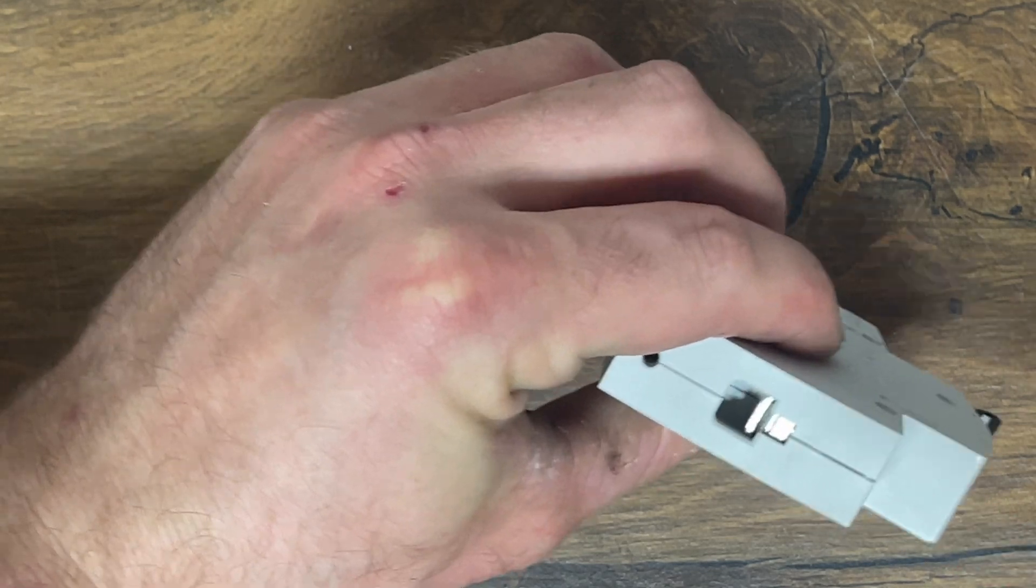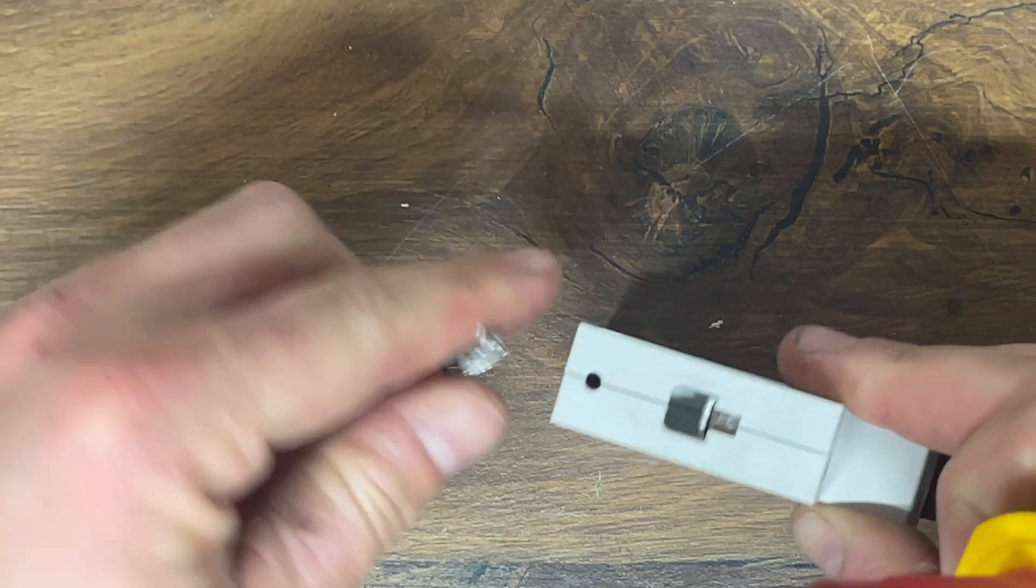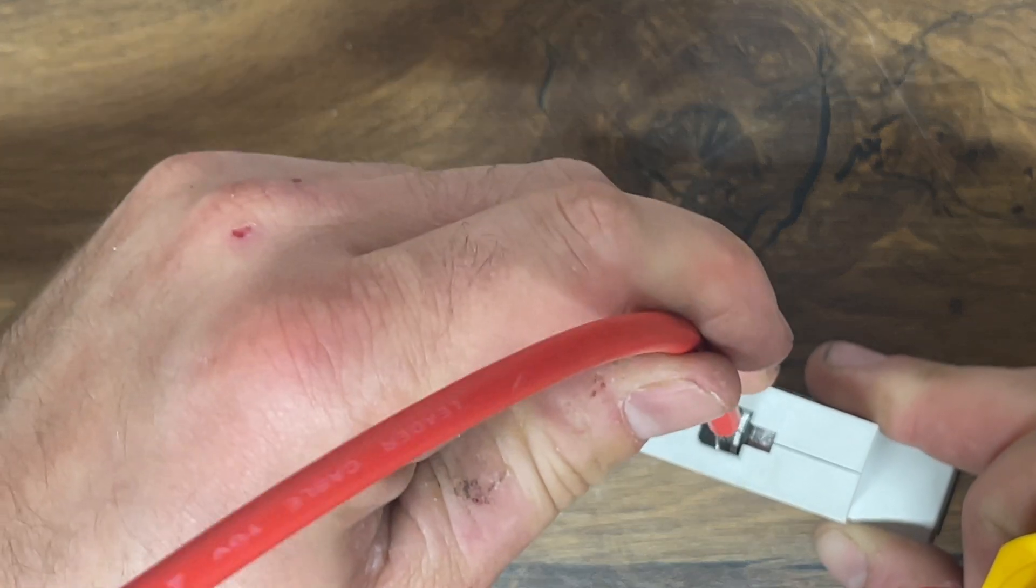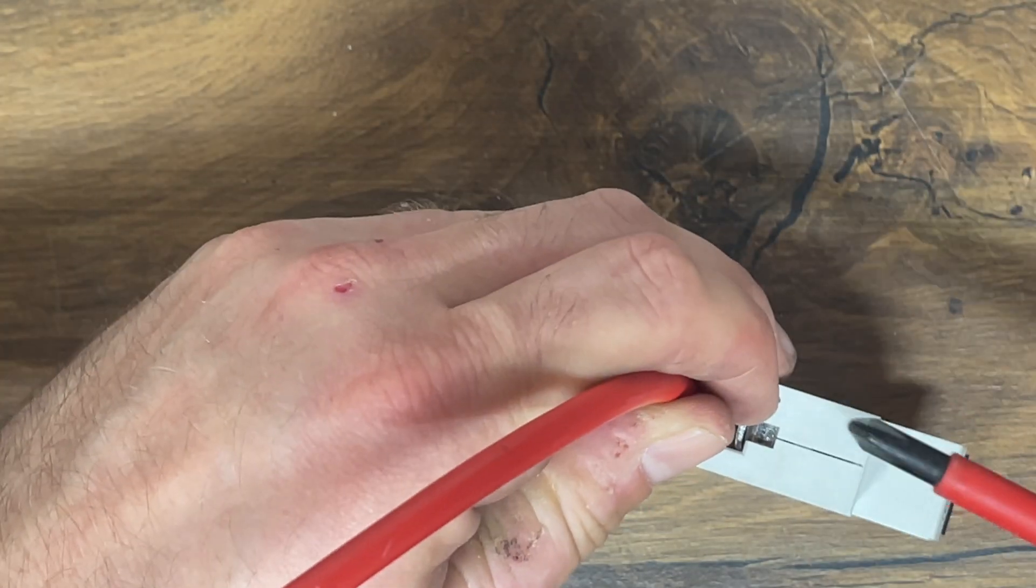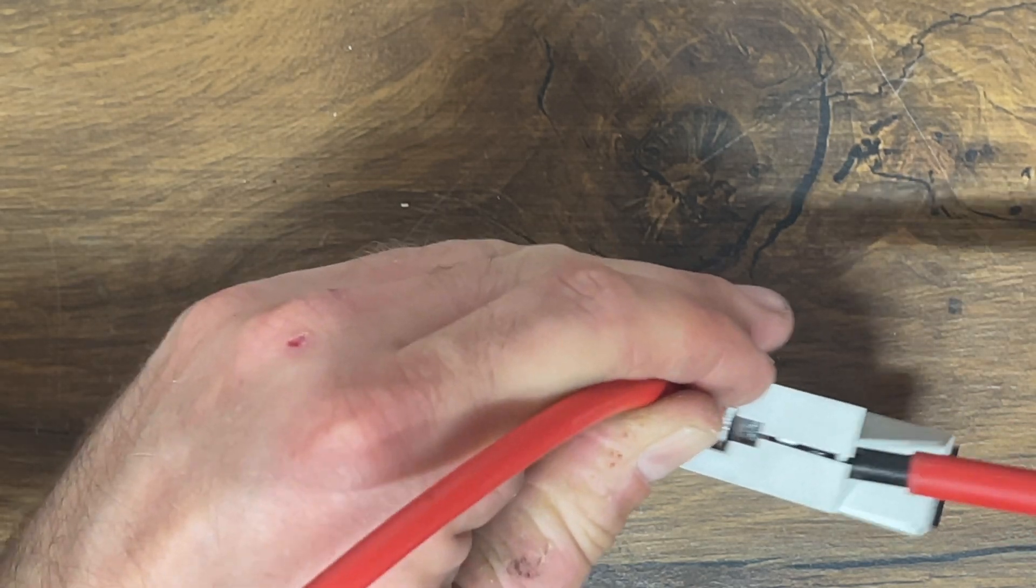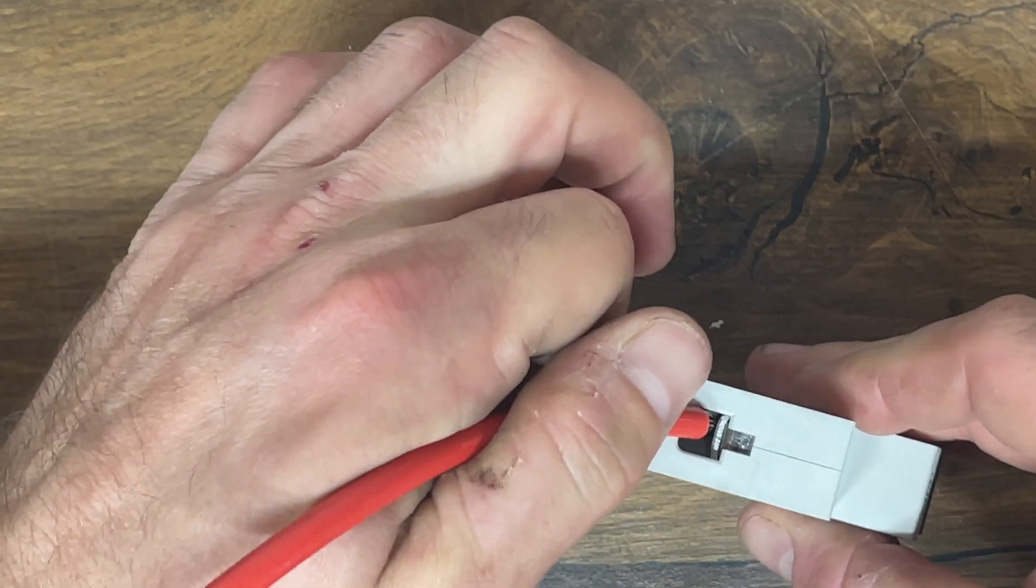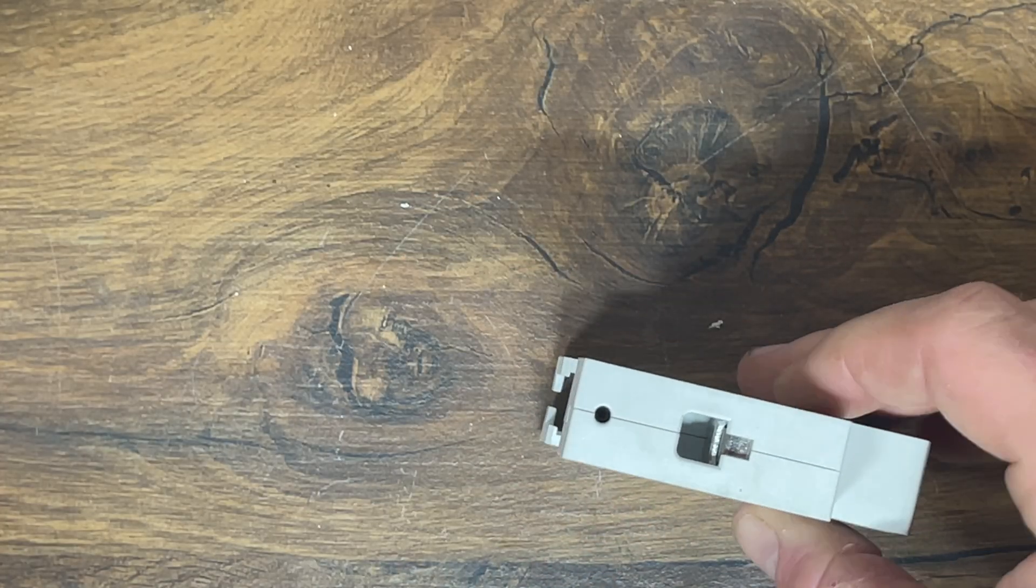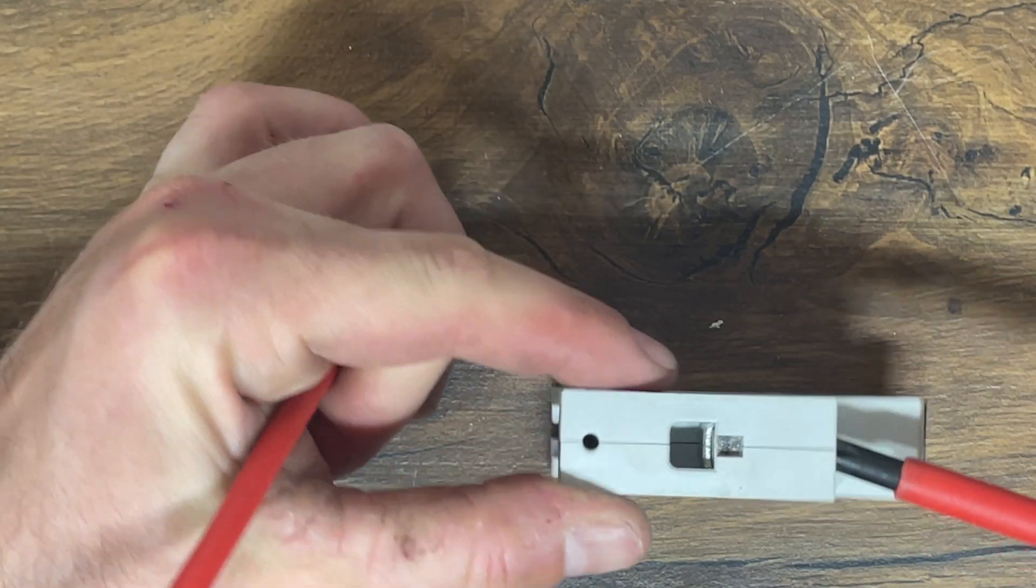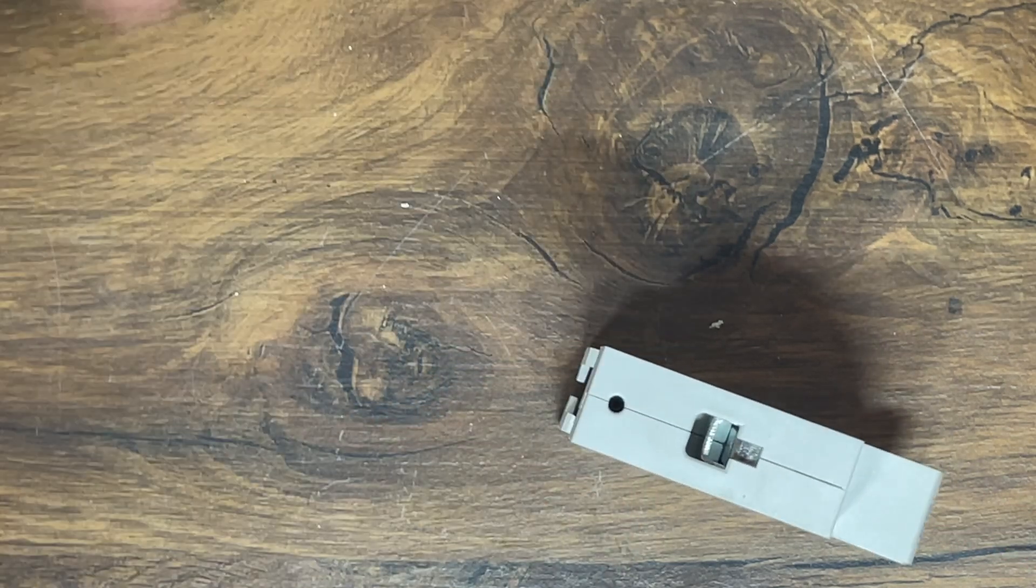The other two main parts on the outside are our screw-down terminals. It could be easy with an MCB to end up putting the cable or a bus bar behind that, and then you screw that down. You think it's secure, and it isn't. This is particularly a problem with the bus bar. As you slot an MCB into the DIN rail, you could think it's secured in place. You can't do the tug method on the cable.